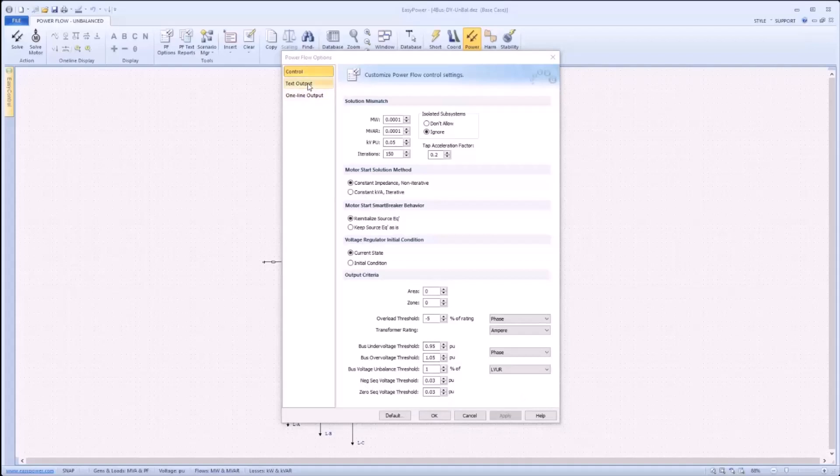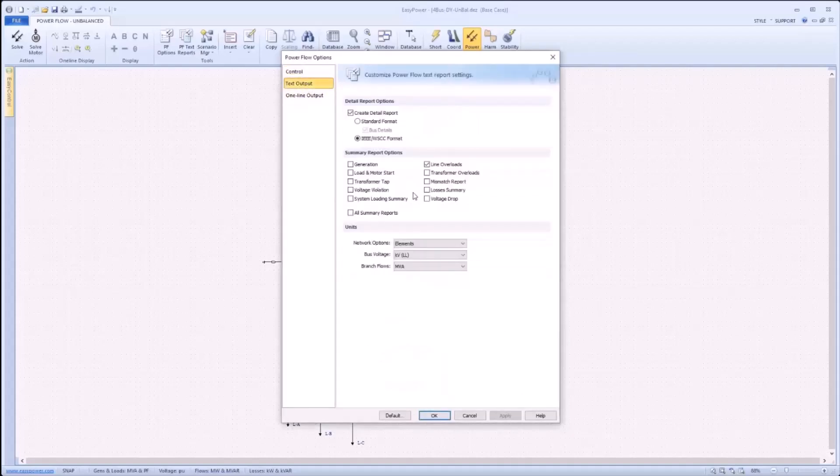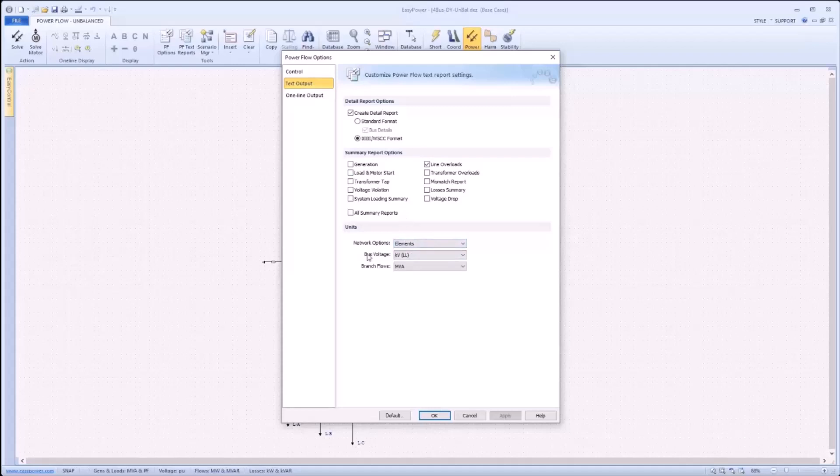Moving to the text output tab, one will see that this menu allows for a variety of summary reports to be generated as well as options for generating a detailed report if desired. The standard detail report contains additional information as compared to summary. For example, when the network option is set to elements, a detailed report will show information for all phases A, B, C, and N. The units section is used to designate the units the report will use to display results. There are options for bus voltage and branch flows with a variety of options. The network option dropdown, as previously mentioned, specifies the report format. Positive sequence only will include only results using positive sequence quantities, while symmetrical components will use all three symmetrical component values, positive, negative, and zero sequence. Finally, the elements option reports quantities for each phase A, B, C, and N.